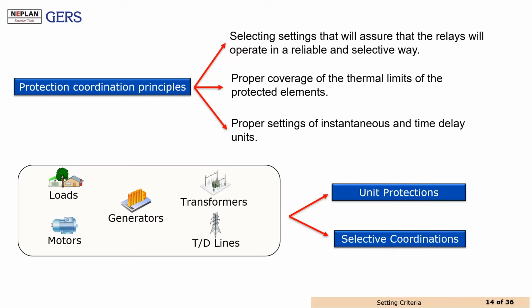The other is the proper coverage of the thermal limits, which is more related to the magnitude of the current. In general, we have to consider the thermal limits in order to send tripping orders for the disconnection of the fault, since any fault can cause thermal violations of elements like transformers, transmission and distribution lines, generators, machines, and for sure, the users. Finally, proper settings of instantaneous and time delayed units. That opens the opportunity to implement selective coordination, which is mainly composed of two types of protection schemes that I will illustrate later: overcurrent protections and distance protections. The other kind of protections are known as unit protections, since when they detect the pickup, they send an instantaneous order, typically in order to disconnect the system.